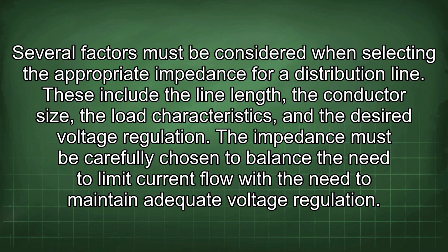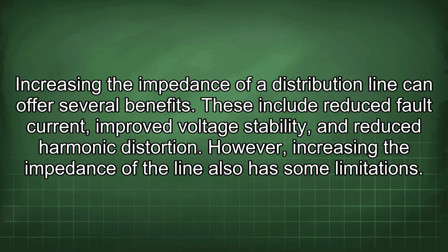These include the line length, the conductor size, the load characteristics, and the desired voltage regulation. The impedance must be carefully chosen to balance the need to limit current flow with the need to maintain adequate voltage regulation. Increasing the impedance of a distribution line can offer several benefits. These include reduced fault current, improved voltage stability, and reduced harmonic distortion.